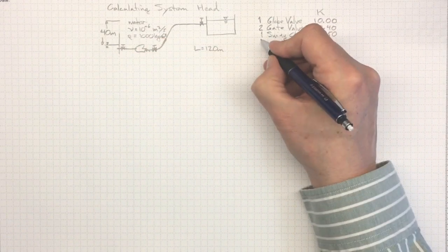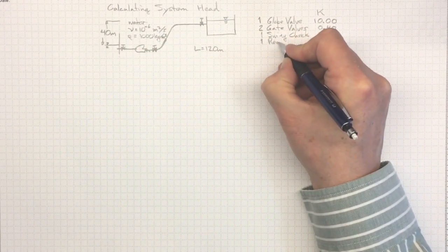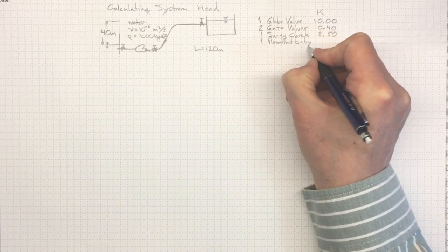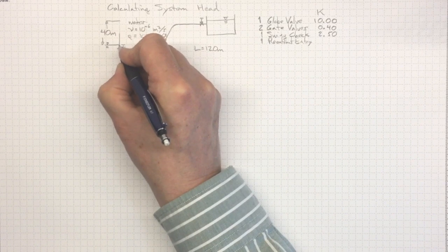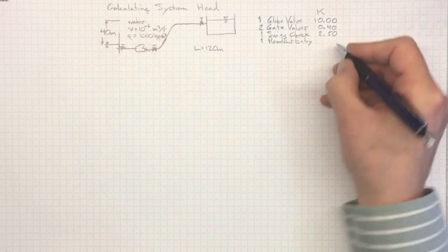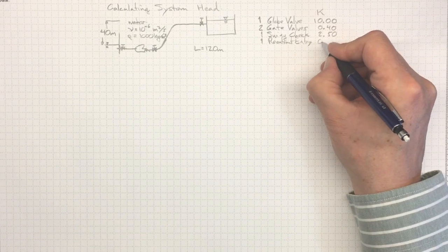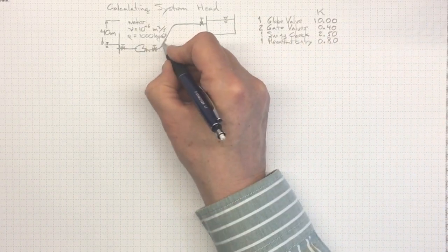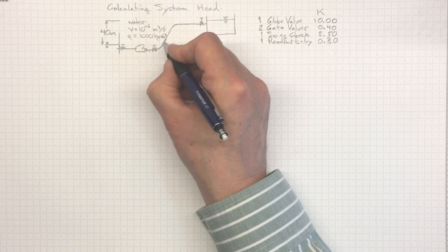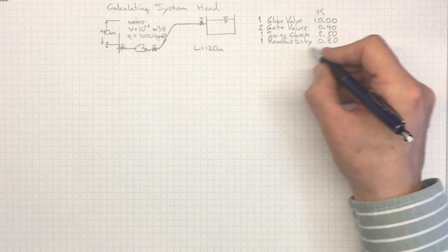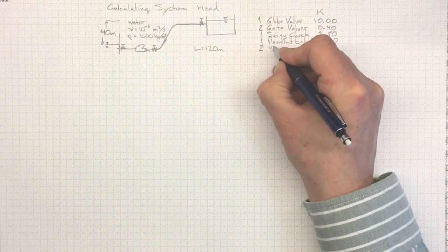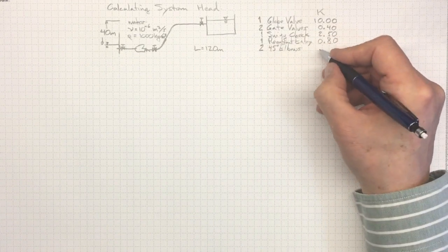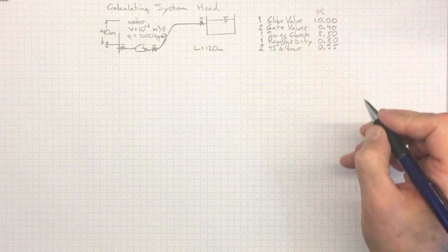This re-entrant entry, and re-entrant means that the pipe sticks out past the wall of the reservoir here, that re-entrant entry will have a K factor of about 0.8. And if we've got two 45 degree elbows here, they'll be maybe a total of about 0.35, assuming that we have long radius elbows.